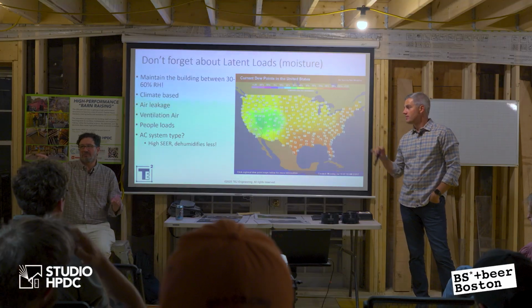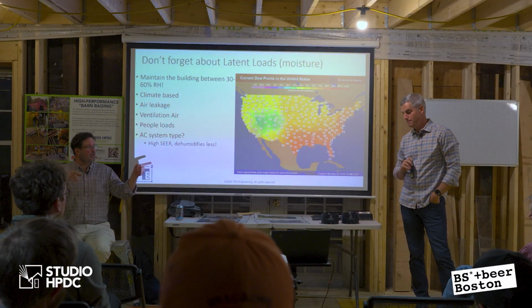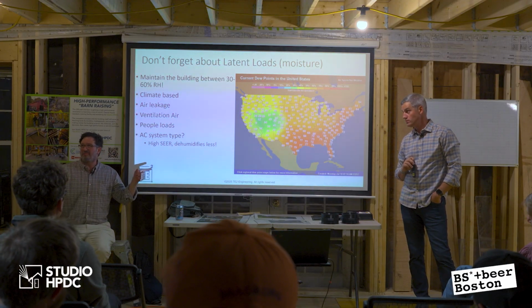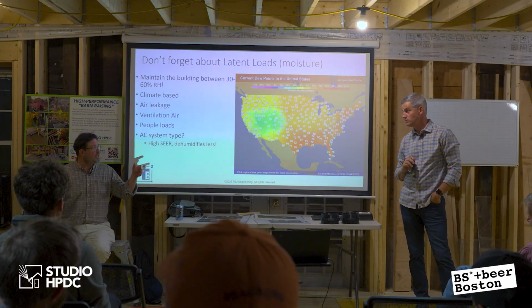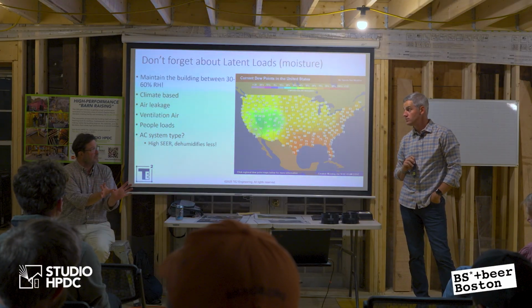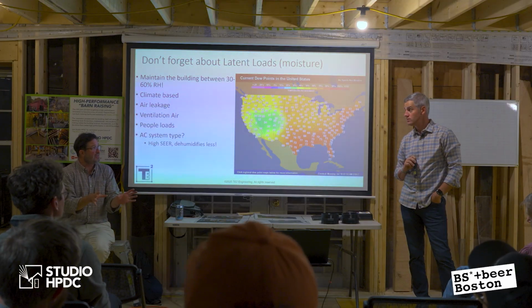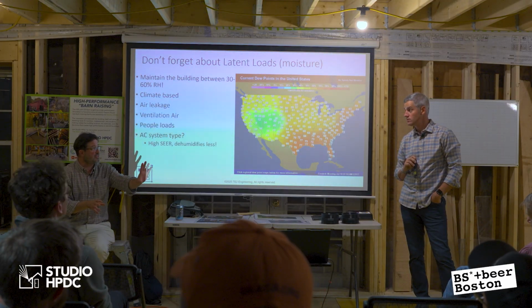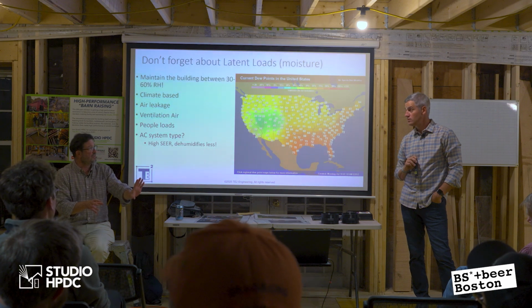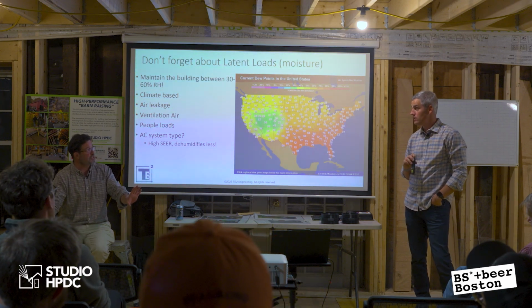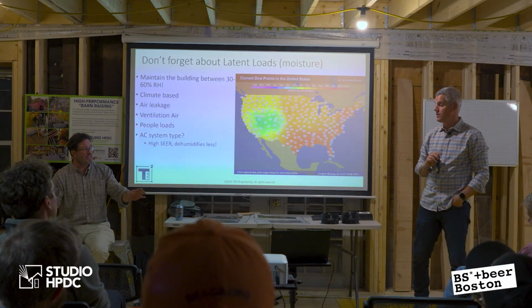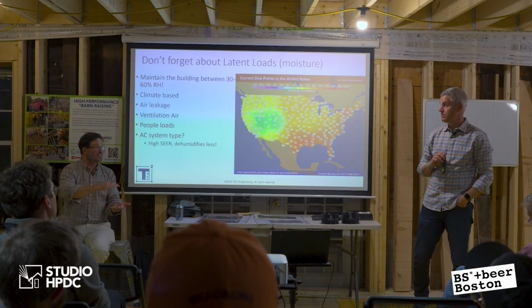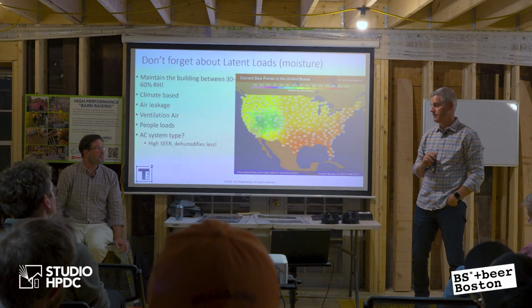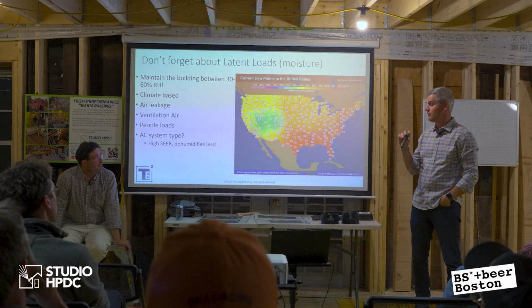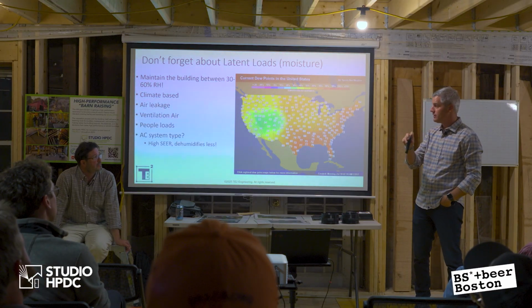You just answered my question, but I want to double check with you. So there's the added equipment, the added amperage, the added cost. But if you have these two in the same machine, is it ultimately net more efficient than having a super high efficient sensible system and then a separate dehumidifier? Is it automatic that the net would be better, even taking a hit on the sensible efficiency? Yes. The net overall efficiency is better if you can run an air to water heat pump as opposed to a ducted dehumidifier.